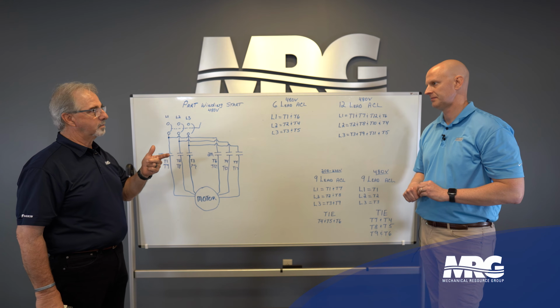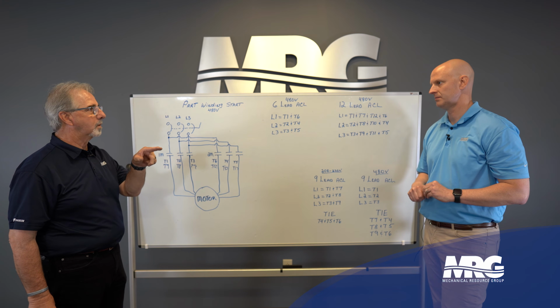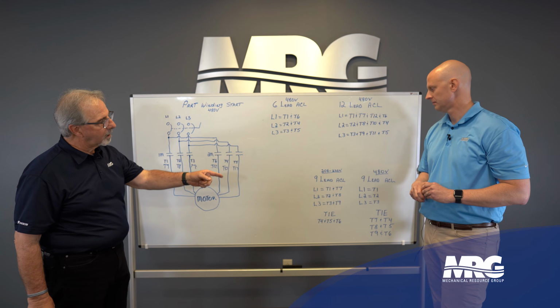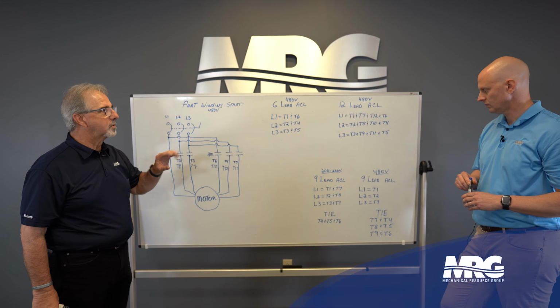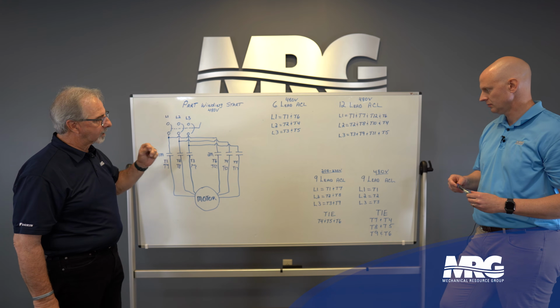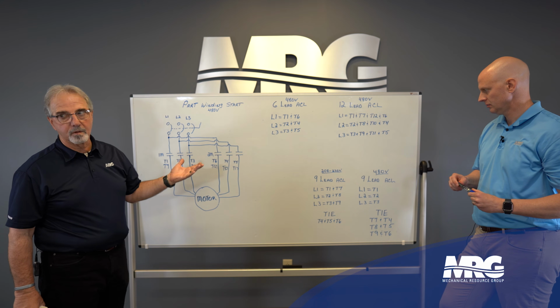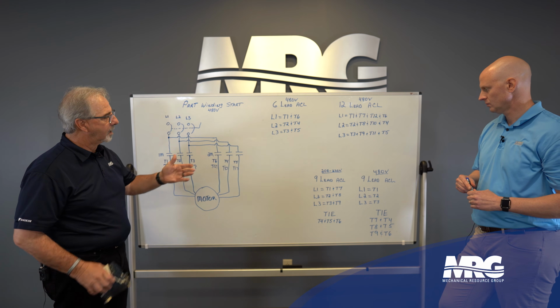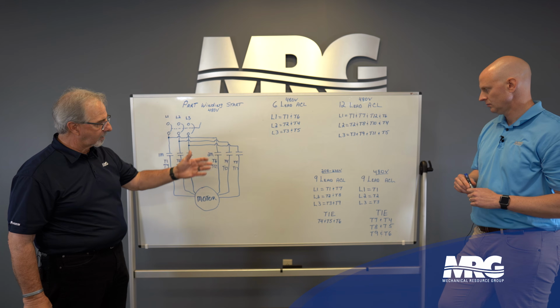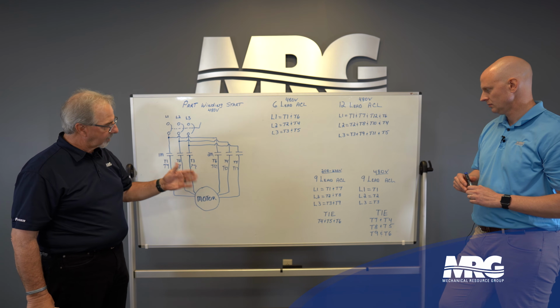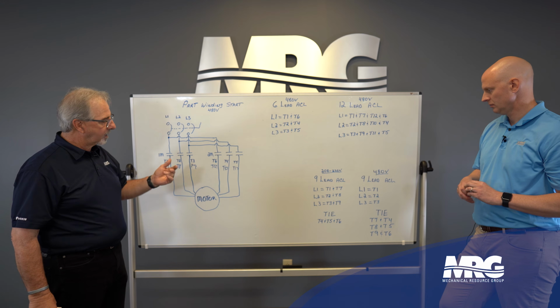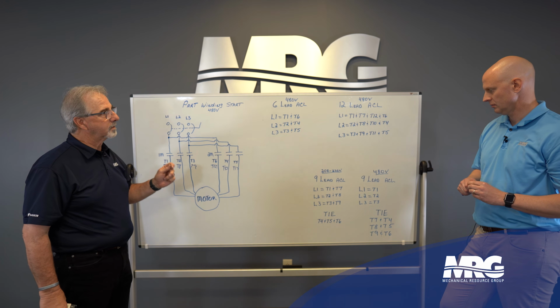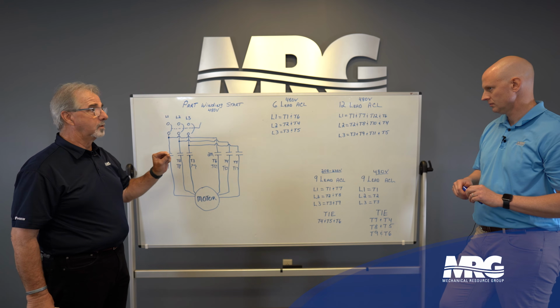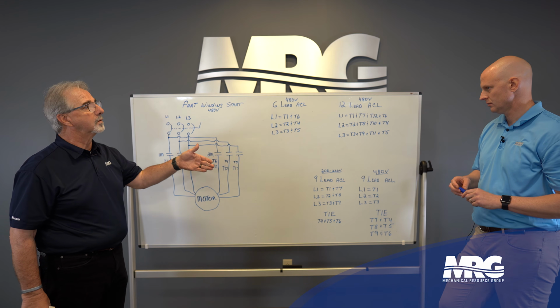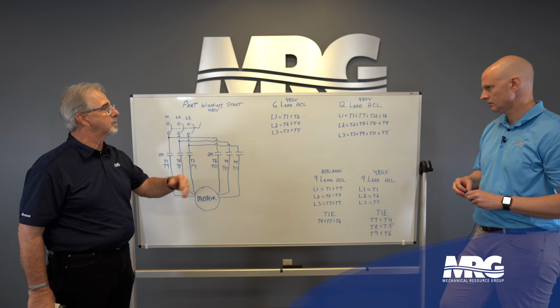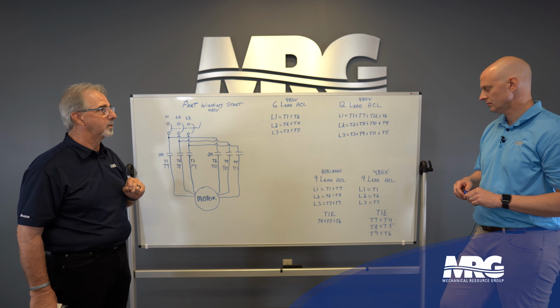Now, we talked about a 9-lead motor. A 9-lead motor was just like what we opened up over there. So what I've done down below here is give you the standard dual voltage connection tying leads together. If you'll notice, ACL stands for across the line. That would be just a contactor and an overload. So L1 would be T1 and T7, T2 and T8, L3 would be T3 and T9. And then you tie motor leads 4, 5, and 6 together. This is for either 208 or 230, considered a low voltage connection. Across the line starting, variable frequency drive, soft start, whatever, that's how we would connect a 9-lead.